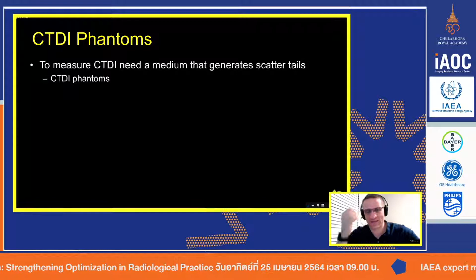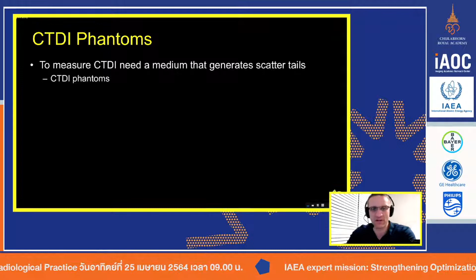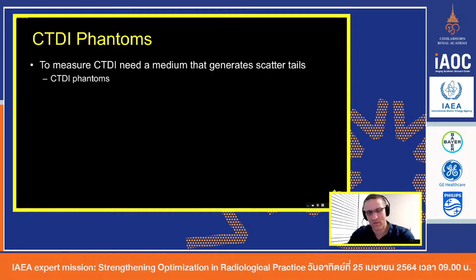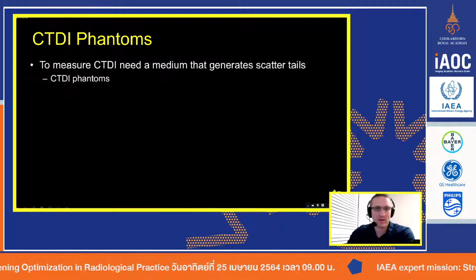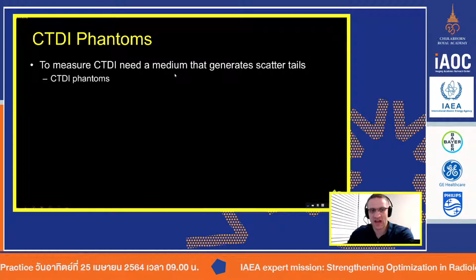Now, the Computed Tomography Dose Index was, as the name implies, made for CT scanners, traditional, not fluoro systems, but actual CT scanners you see in radiology. So I'm going to talk a little bit about the origins of CTDI, and we'll obviously see why and where CTDI works and doesn't work for the spin fluoroscopy cone beam CTs. So to measure CTDI, you need some way to create scatter. So that is why we use CTDI phantoms.